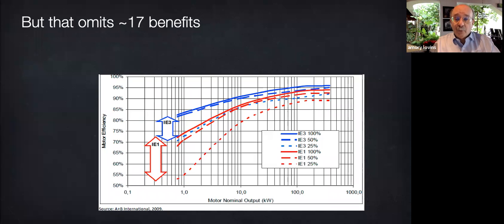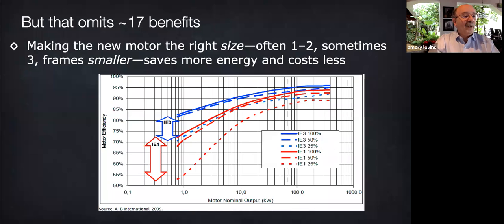So you can reduce distribution losses and capacity needs with better power factor that comes for free as part of the better motor. Premium motors run cooler for lower resistive losses. The cooler the copper, the less the resistance. That also increases the life of the motor because each 10 Celsius degrees of reduced temperature roughly doubles expected life of things that otherwise deteriorate with heat like insulation and lubricant. Longer grease life means less downtime and less frequent lubrication. You start to see a bunch of cascading savings here.